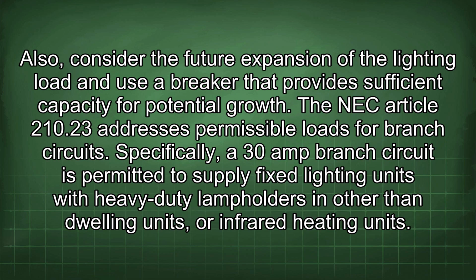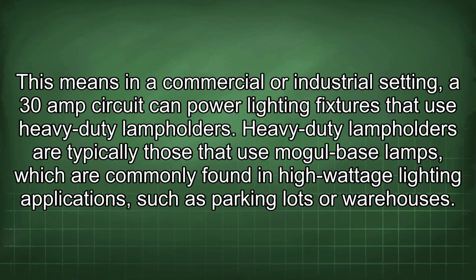The NEC Article 210.23 addresses permissible loads for branch circuits. Specifically, a 30 amp branch circuit is permitted to supply fixed lighting units with heavy-duty lamp holders in other than dwelling units or infrared heating units. This means in a commercial or industrial setting, a 30 amp circuit can power lighting fixtures that use heavy-duty lamp holders. Heavy-duty lamp holders are typically those that use mogul-base lamps, which are commonly found in high-wattage lighting applications, such as parking lots or warehouses.